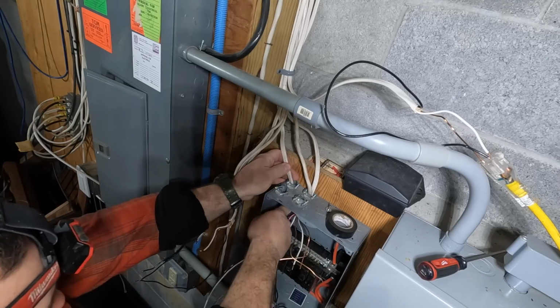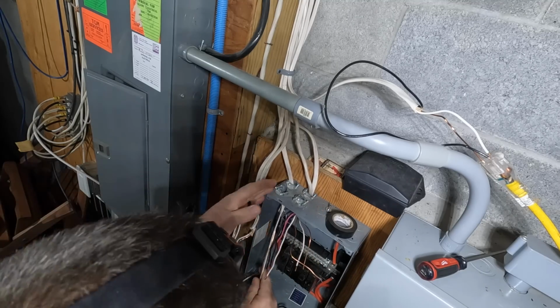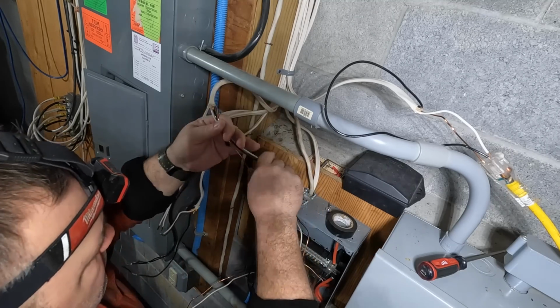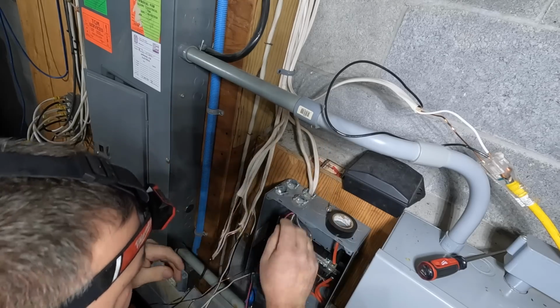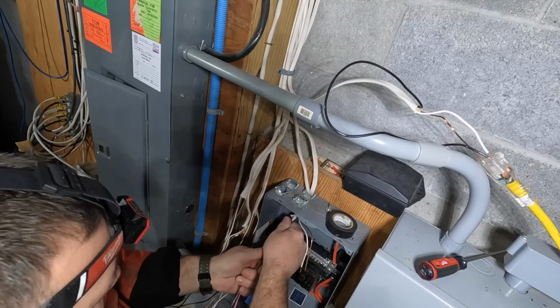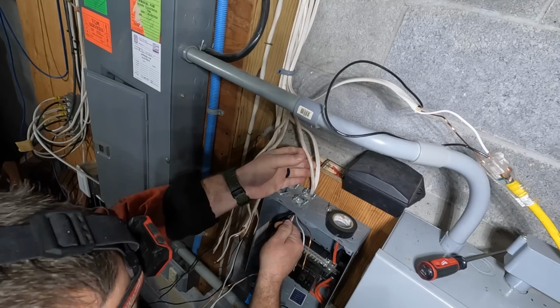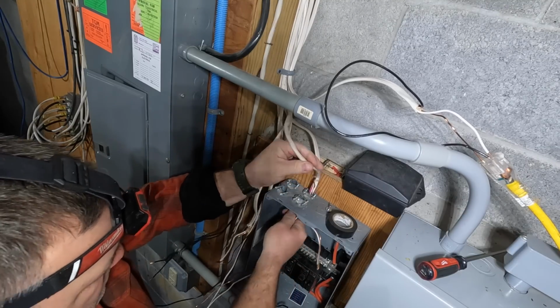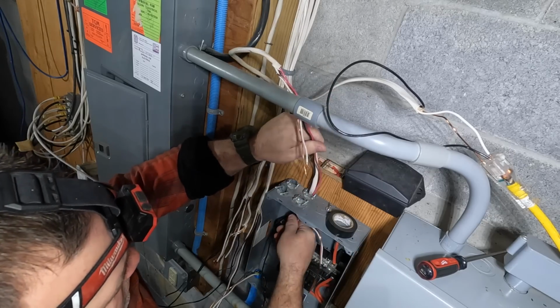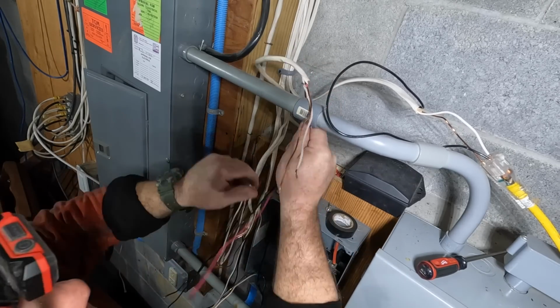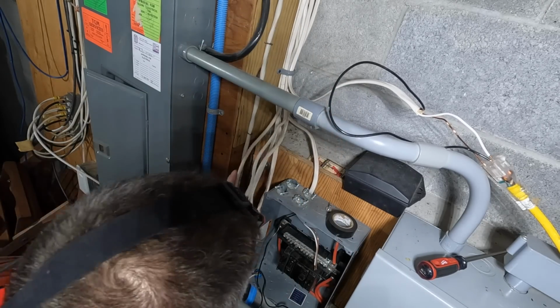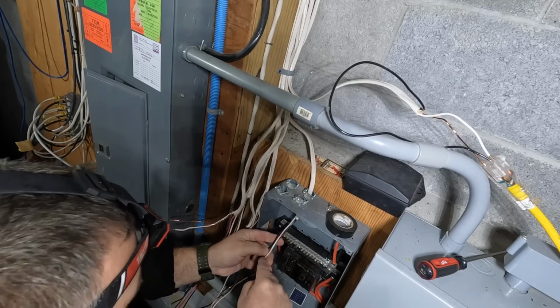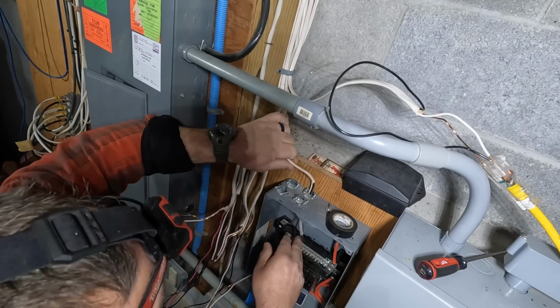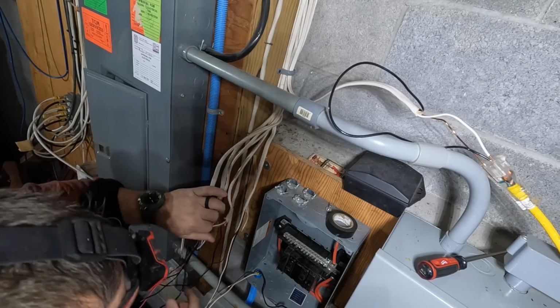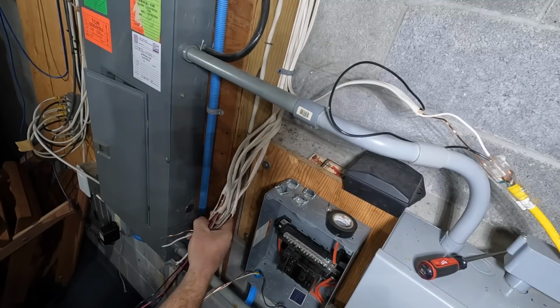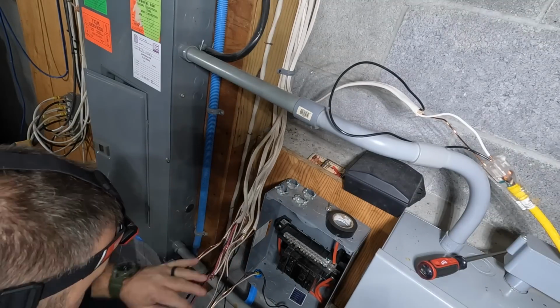The other thing we must do with a multi-wire branch circuit is use a common trip double pole circuit breaker so that we could disconnect all ungrounded legs while we work on the circuit, because the neutral would have current if only one of them was on. Obviously, when you're pulling these out, you're just trying to straighten them out so they come out easily without damaging the insulation on the conductors. The last thing you want to do is damage the insulation and have to make a repair or a splice that's not necessary, that actually slows down the progress of the job. So be careful not to nick the insulation on any of the conductors during a service upgrade.